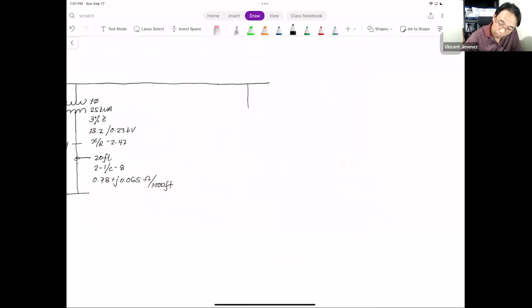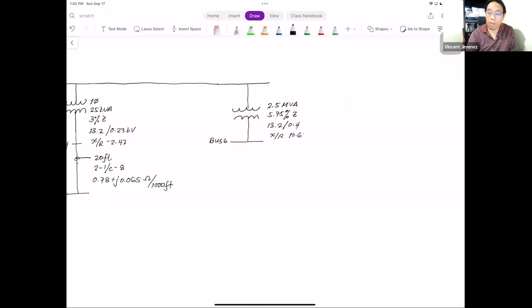Okay. This time I will neglect the cable. We are running for the short circuit at this bus number 6. Okay, so the data for this transformer is a 3-phase transformer, 2.5 MVA, 5.75% Z, and X over R ratio. Okay, the voltage rating is 13.2 down to 400 volts. Okay, typical installation sa locality natin. Okay, Meralco provides now 400 volts for the 3-phase system. Okay, wala na yung mga dating 380, puro 400 na yung binibigay sa atin ngayon. Okay, so we have here the X over R ratio for this particular transformer at 10.67.